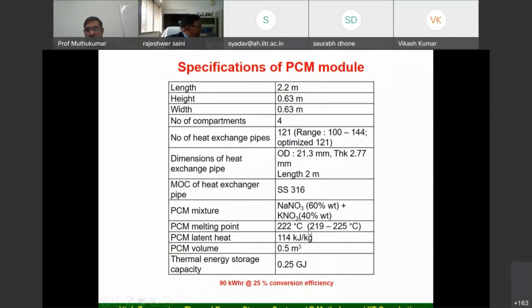This PCM - what happens in the steam accumulator is when you start consuming steam, the pressure will decrease, and because of flashing, the temperature of the steam will drop down. So the main purpose of the thermal storage system is to deliver heat at constant temperature. When there is a decline in pressure, to compensate for the loss, we need to supply auxiliary heat, which can be provided from the PCM.